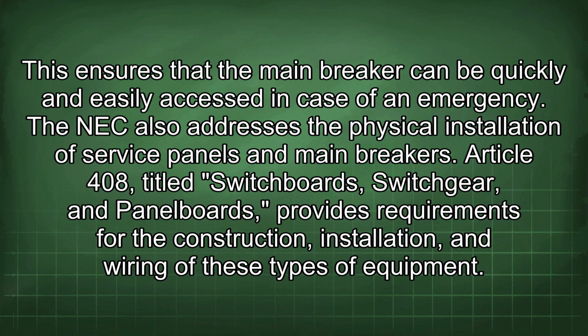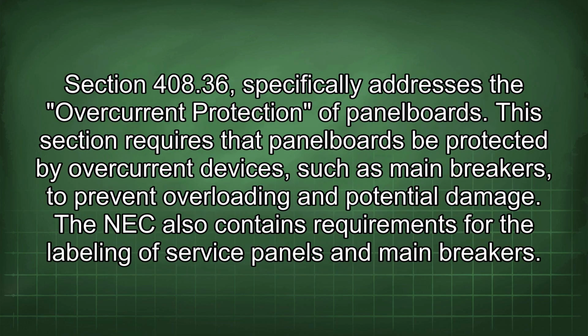The NEC also addresses the physical installation of service panels and main breakers. Article 408, titled Switchboards, Switchgear, and Panelboards, provides requirements for the construction, installation, and wiring of these types of equipment. Section 408.36 specifically addresses the overcurrent protection of panelboards. This section requires that panelboards be protected by overcurrent devices, such as main breakers, to prevent overloading and potential damage.